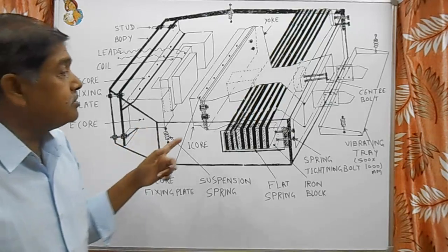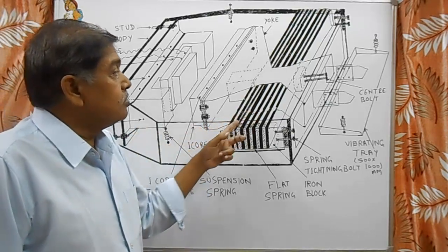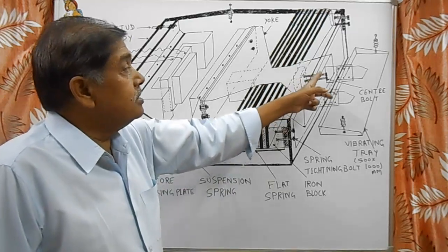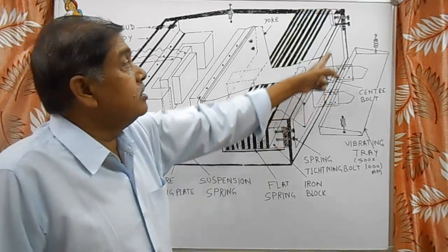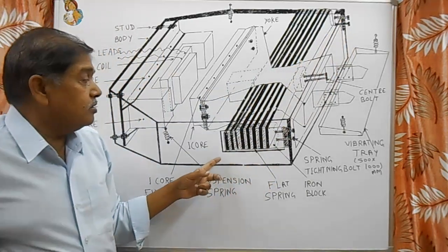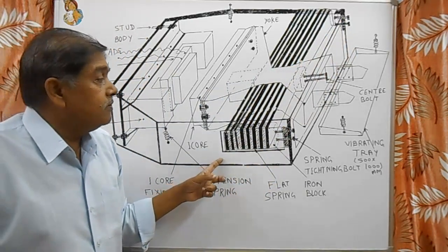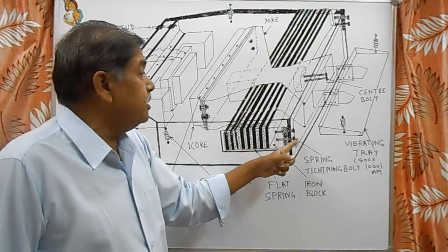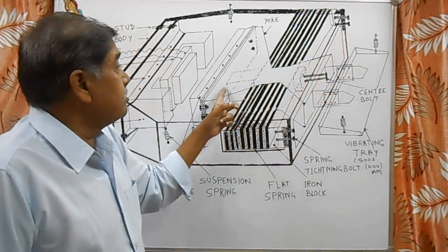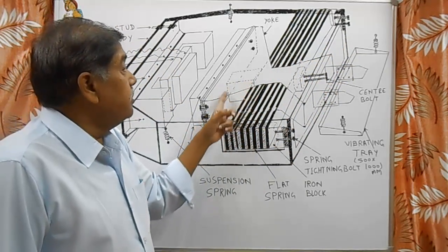In addition to this, sometimes these spring plates are broken, so in that case also feeding is less. Sometimes these center bolts are loose and the side bolts are loose, so feeding will become reduced. To increase the feeding of this feeder, we have to tighten these side bolts completely and the center bolts.